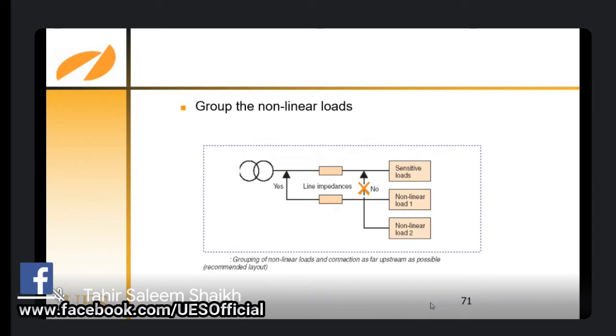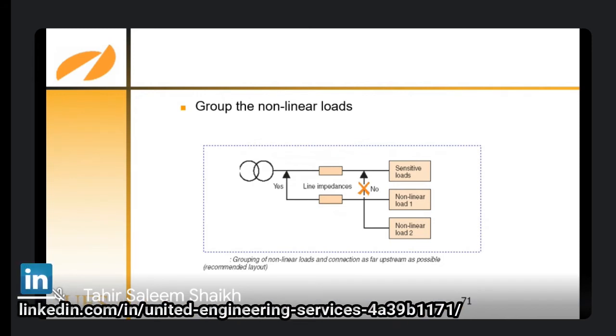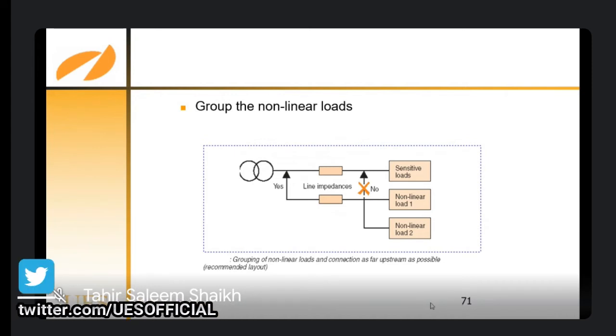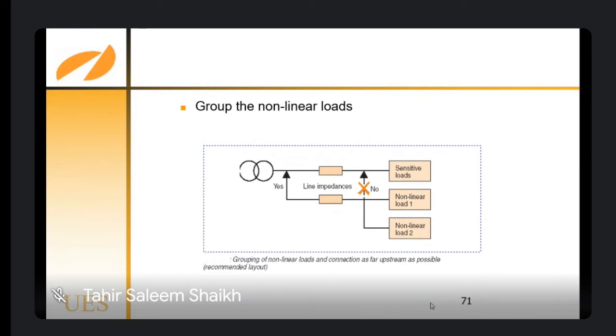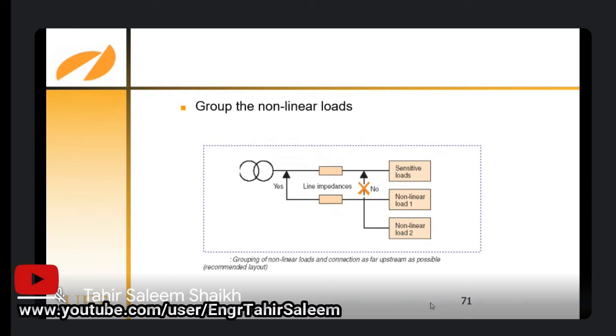This induction furnace, in spite of a passive filter, which I'll come to later on, had a lot of problems because of the harmonics. Their foundry breaker trips, their foundry capacitor burst, and the recommended solution was that the 11 kV supply should be separate for non-linear loads as well as linear loads. For the old plant, it is a difficult task. But for a new installation, you have to be careful about non-linear loads and linear loads. So a designer or a consultant should be aware of this. So that is one solution.